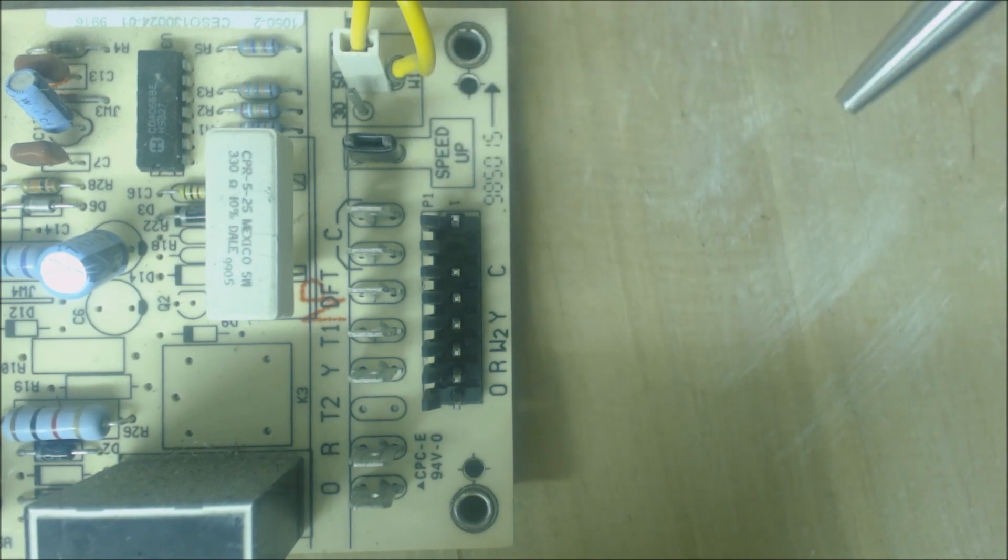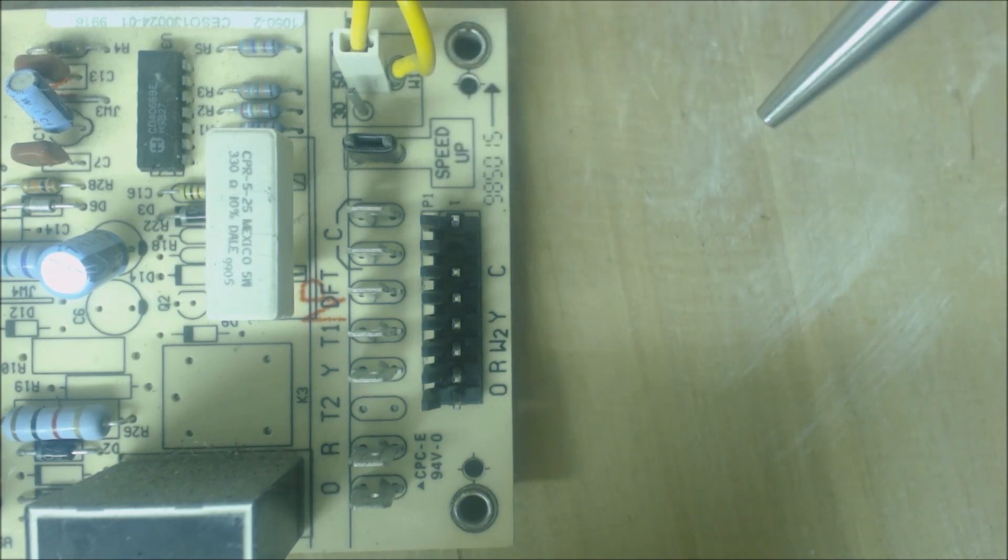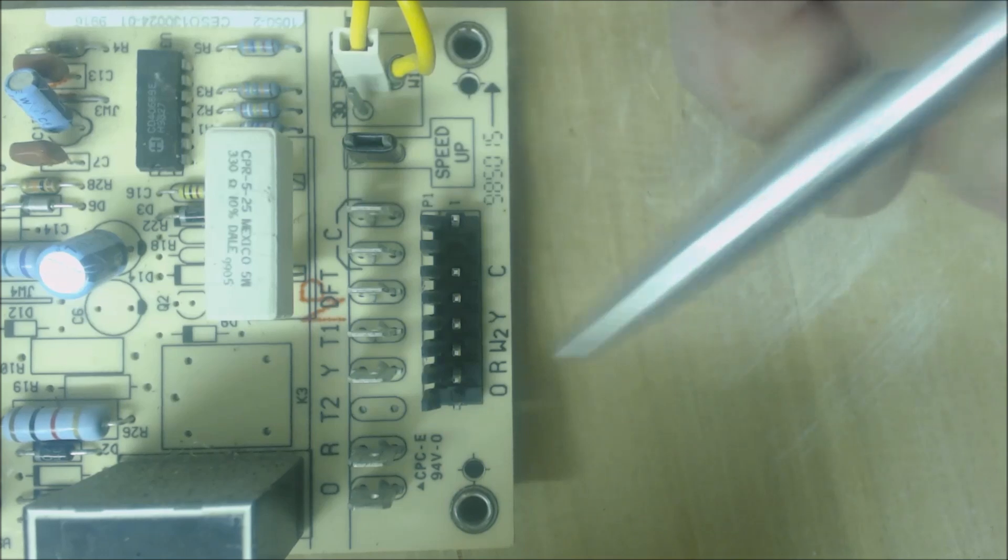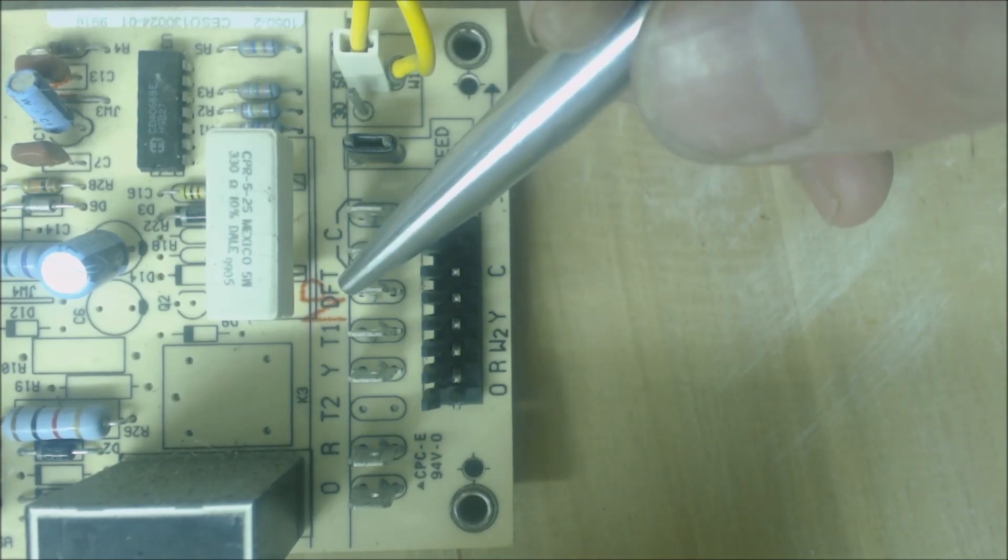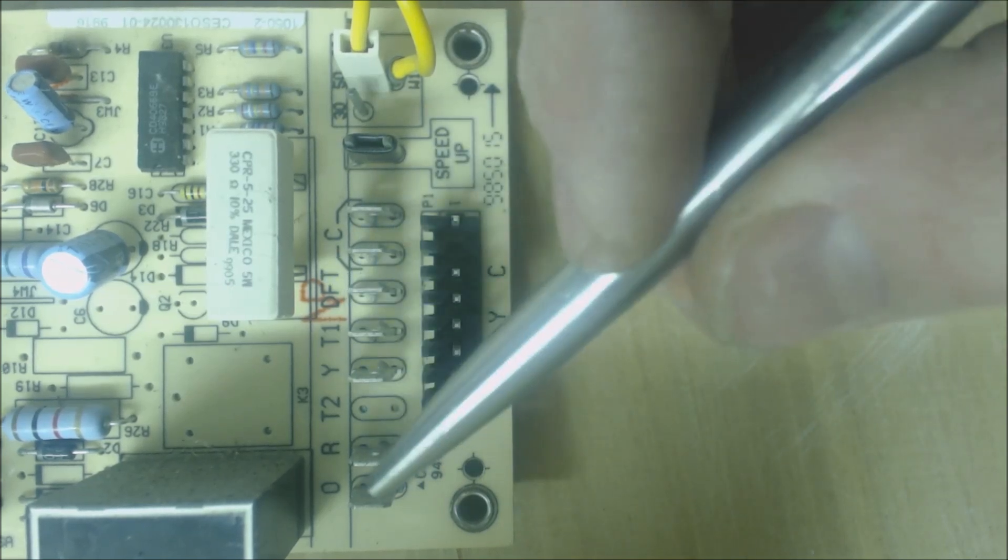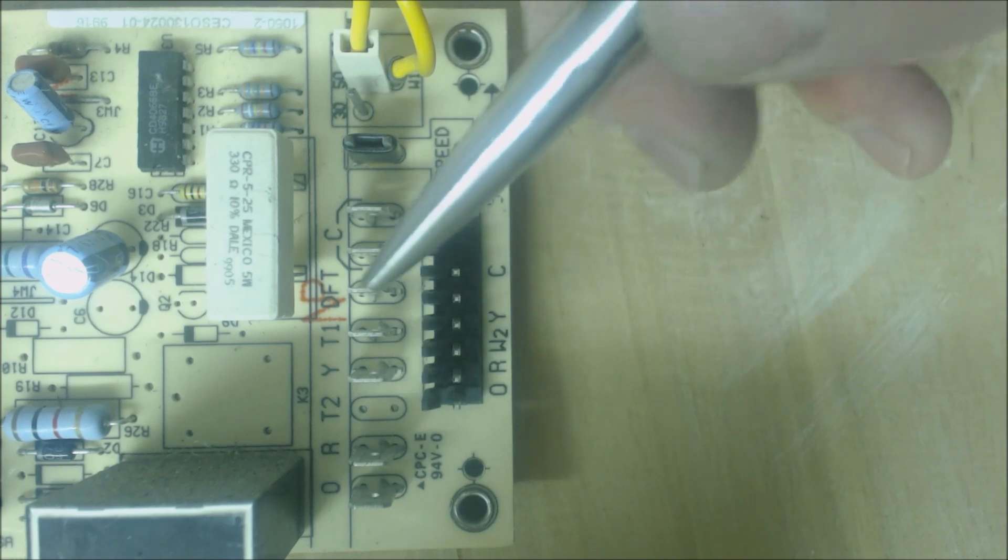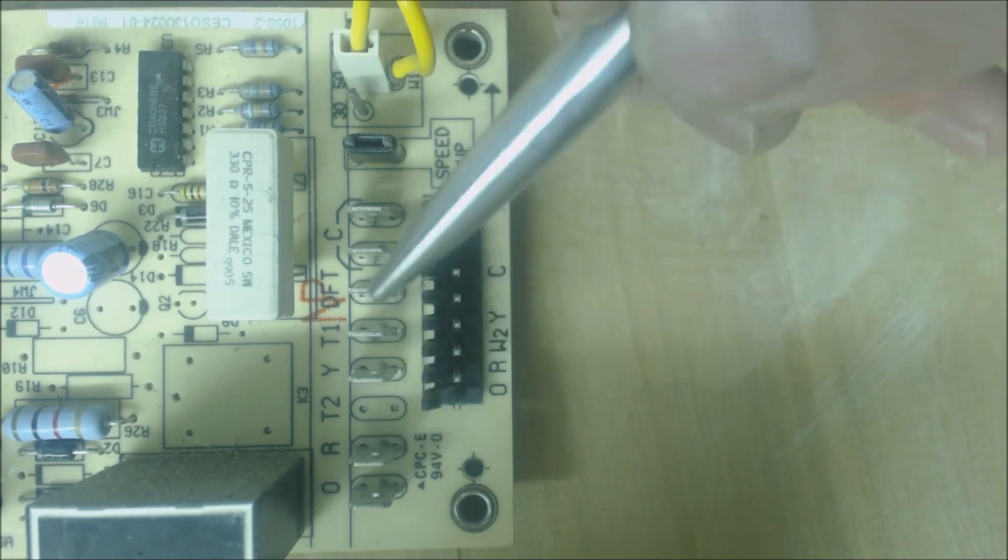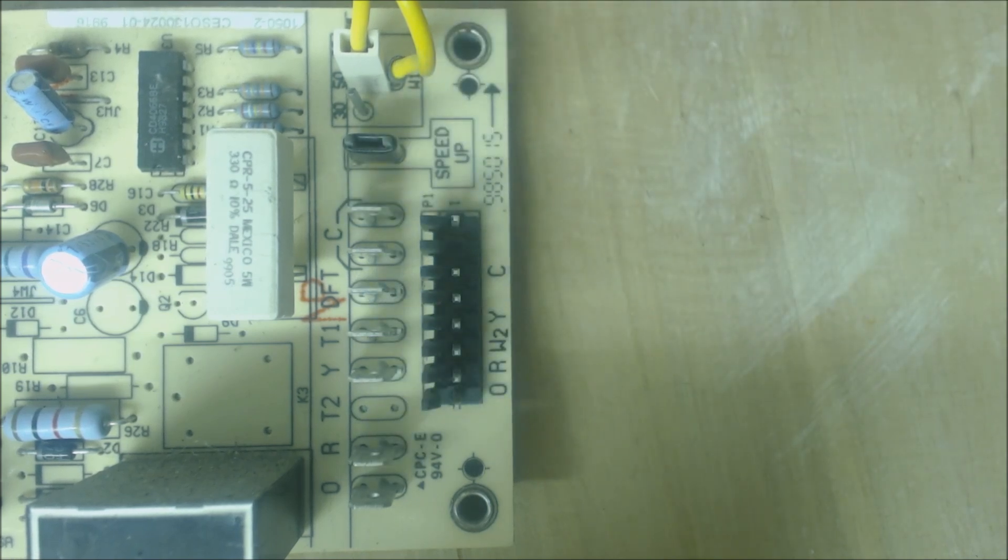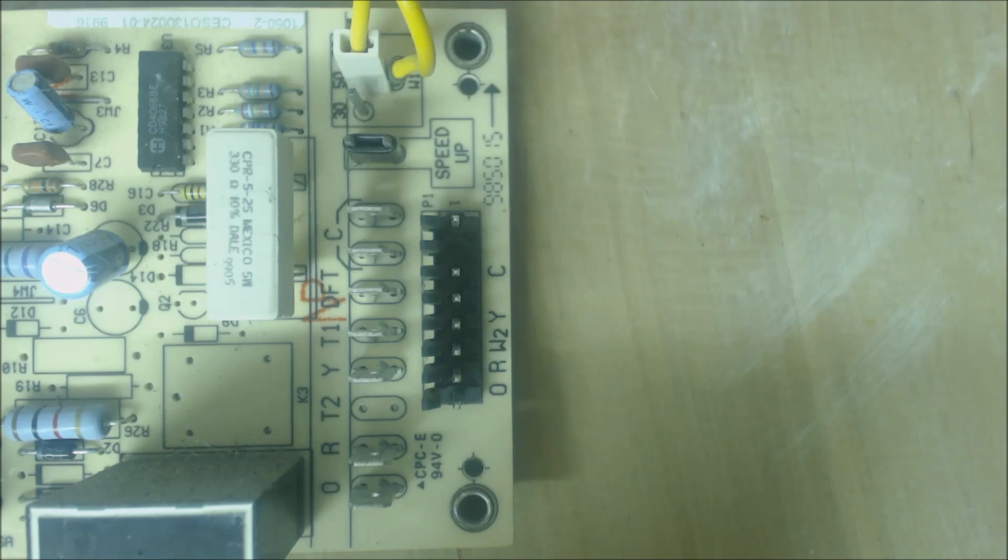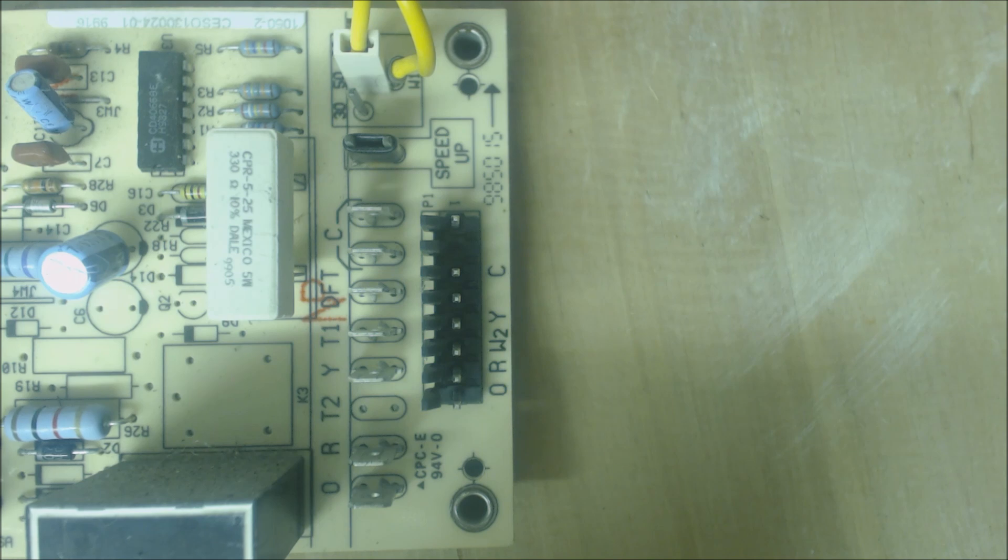Once you're satisfied after you've checked your defrost cycle, you can pull the alligator clip off from DFT to R, and that will open this electrical circuit. The control board will think that the outdoor fins are above 80 degrees. That will get you back out of defrost and back into heat mode.